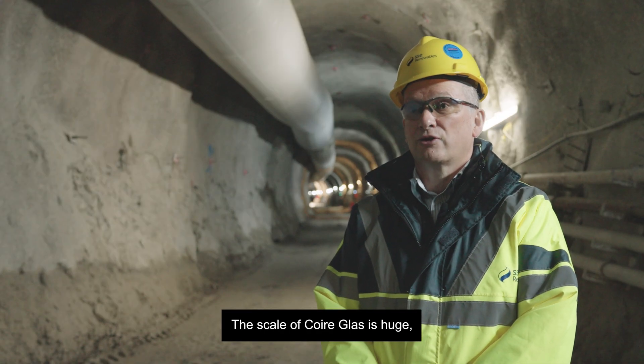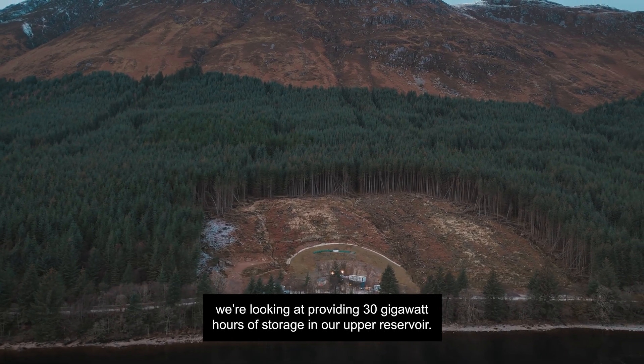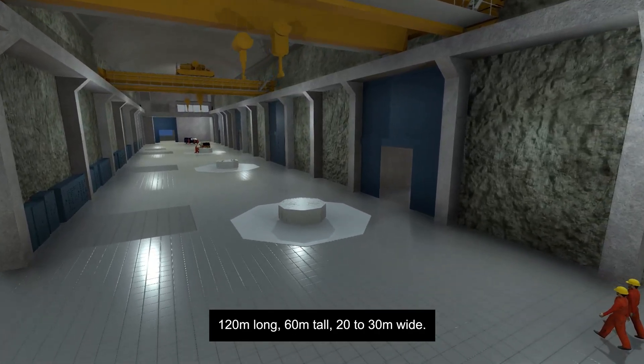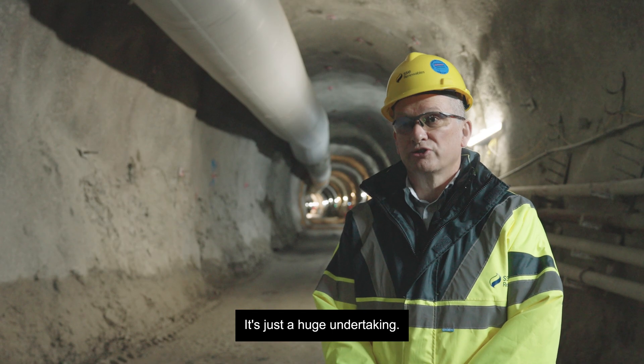The scale of Coire Glas is huge. We are looking at providing 30 gigawatt hours of storage in our upper reservoir. It involves two large caverns built underground — 120 metres long, 60 metres tall, 20 to 30 metres wide. It's just a huge undertaking.